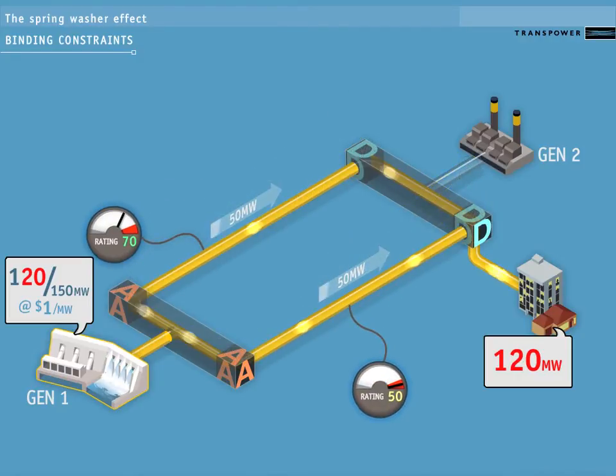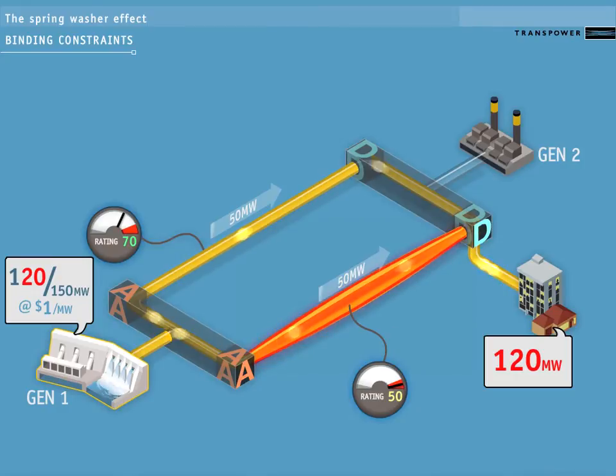Given that it is already carrying 50 megawatts, it is constrained. This is known as a binding constraint on the transmission system. You would think the extra 20 megawatts could be sent through the line with the higher rating. Unfortunately, we can't do that. Kirchhoff's law dictates that the power would be distributed equally between the lines. This means 60 megawatts through each line.